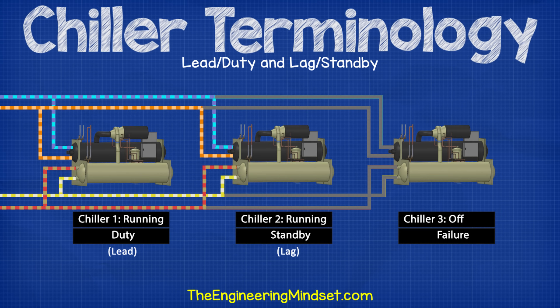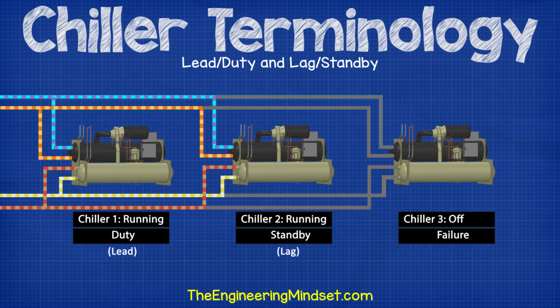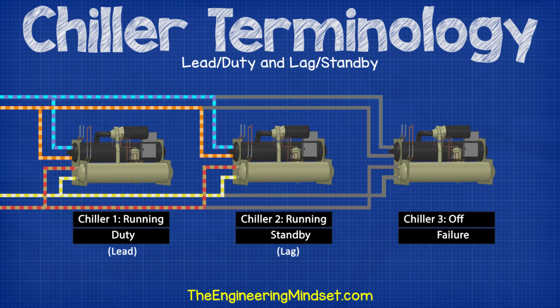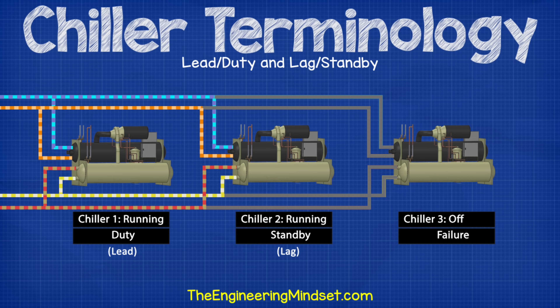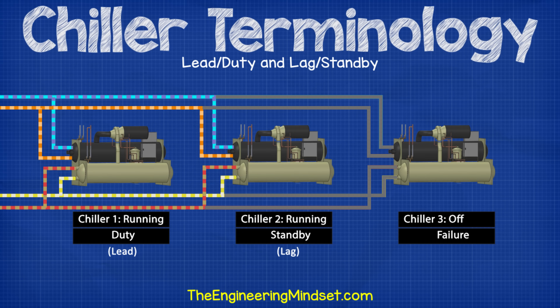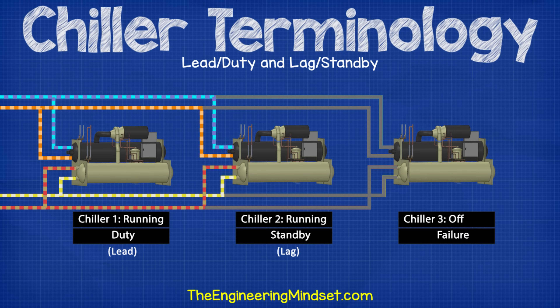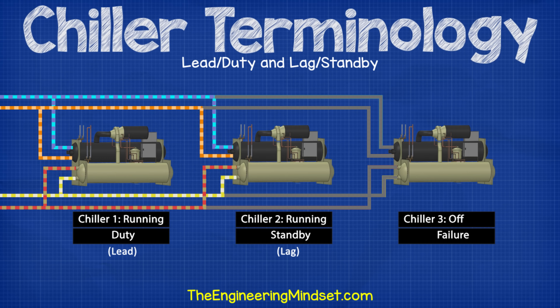Lead and lag, or duty and standby. The lead or duty refers to the chiller or pump which is designated to be the first to turn on and handle the cooling load when a building utilises multiple chillers. A lag or standby refers to the next chiller or pump which will turn on if the lead or duty is either unable to handle the full load, or if the lead/duty chiller or pump shuts down due to a fault. The designation of lead/lag or duty/standby will usually rotate to ensure equal run hours of all the equipment, or it will be designated according to the most efficient equipment running at the current operating conditions.